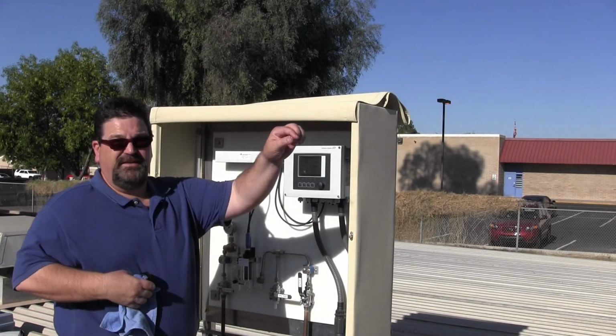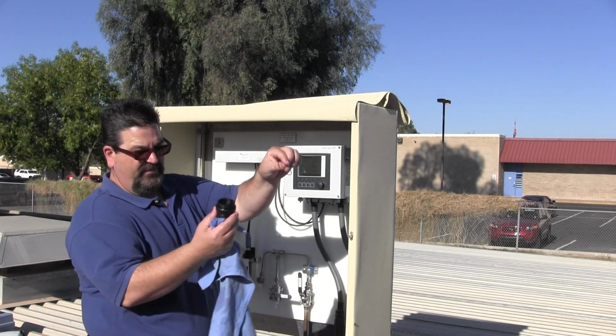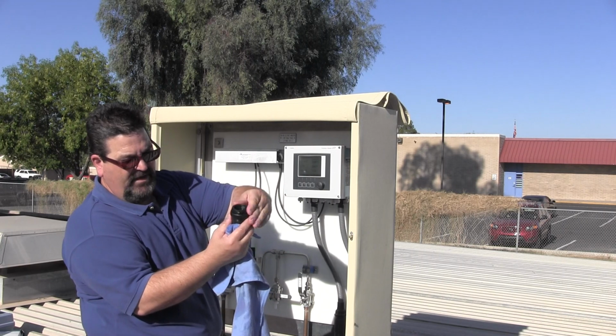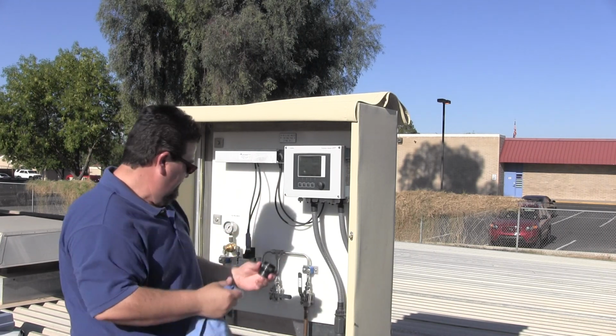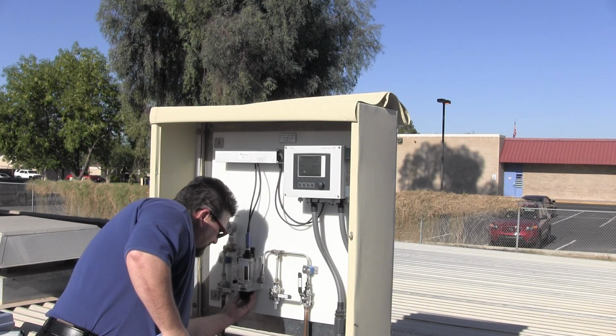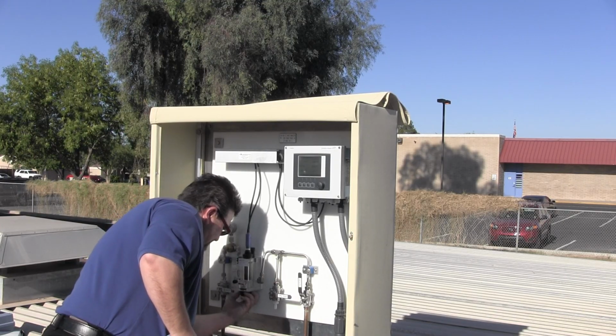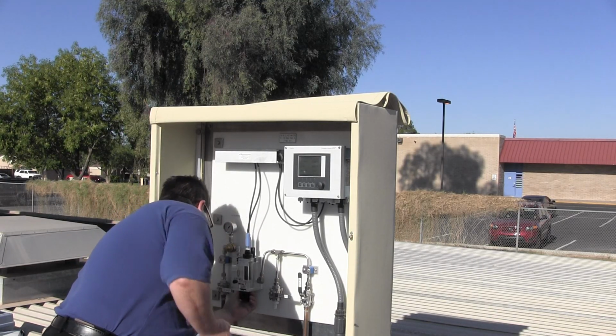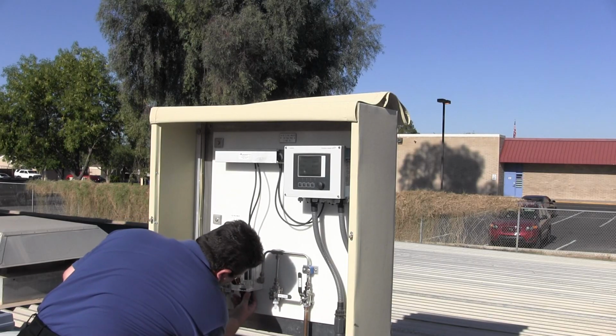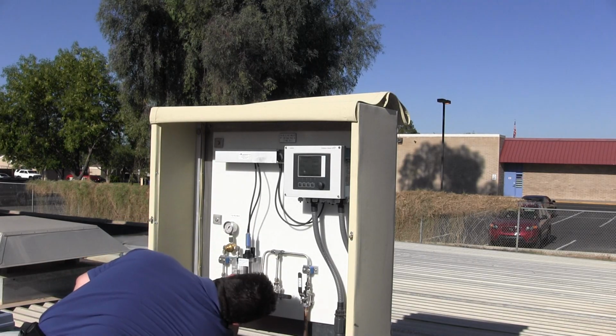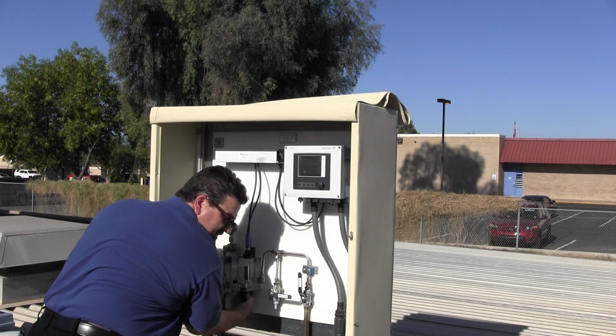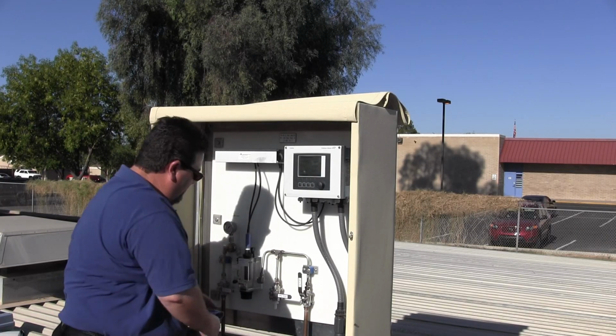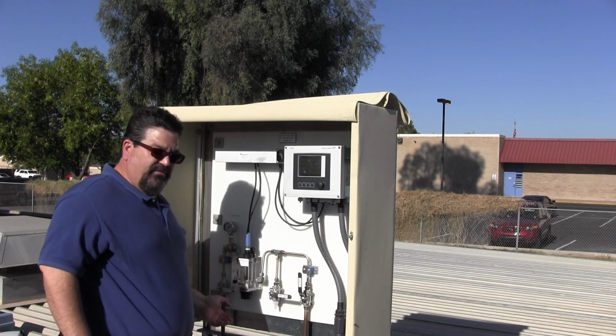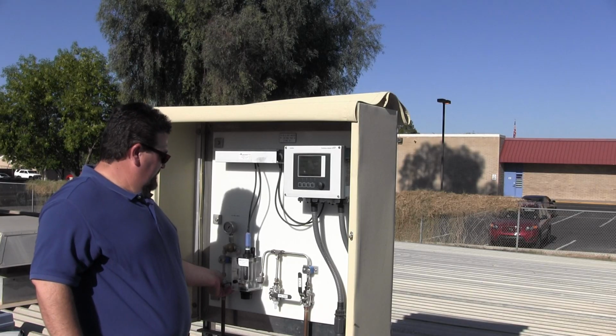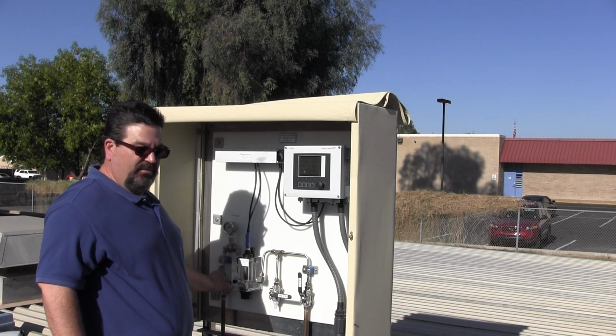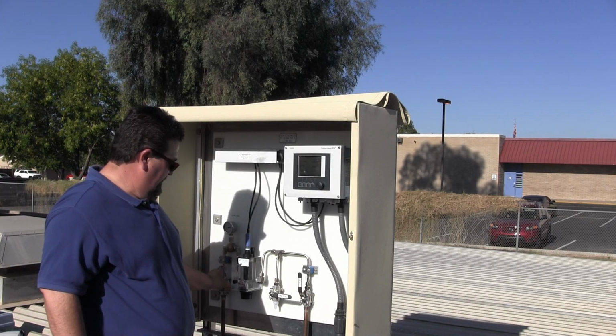The most important thing, make sure that the O-ring that fits on the shallow side of the cup is still on there when you put it back on. I dropped it. Hand tight is all that's required to put the calibration cup back on. Make sure your outlet valve is open. Very gently start your flow back through the block, filling it up with water.